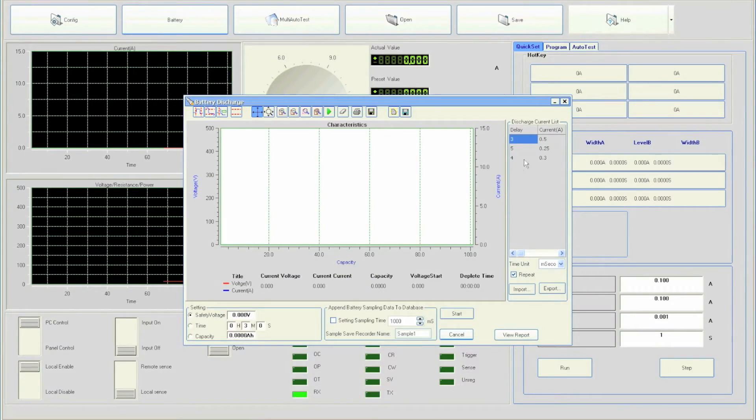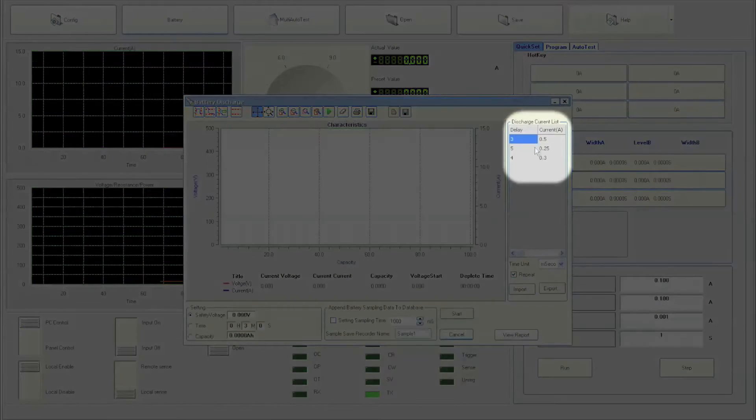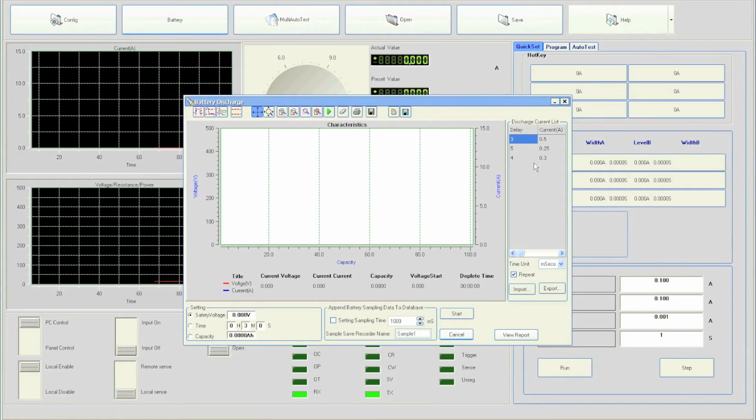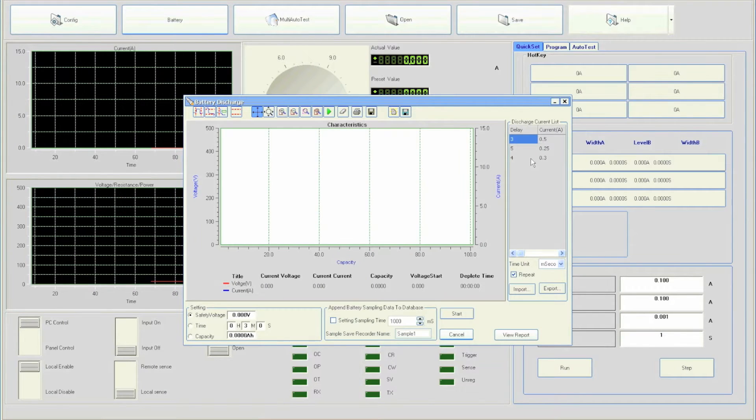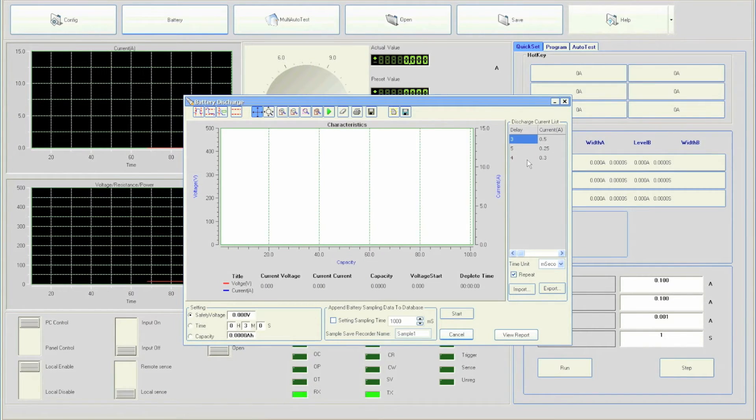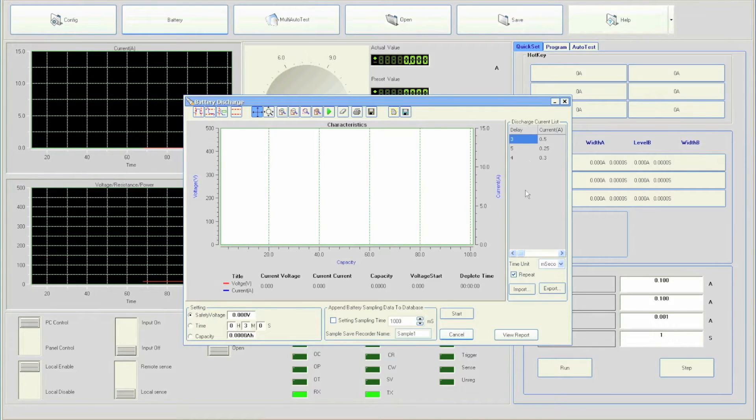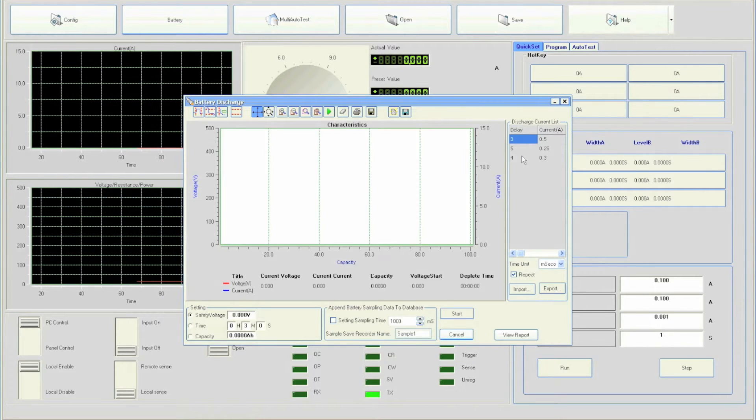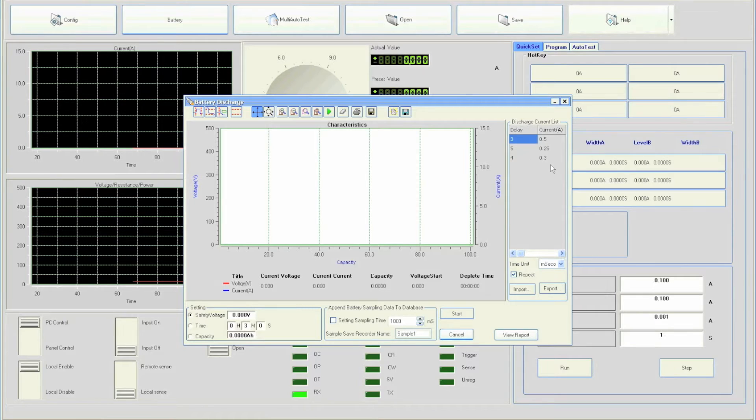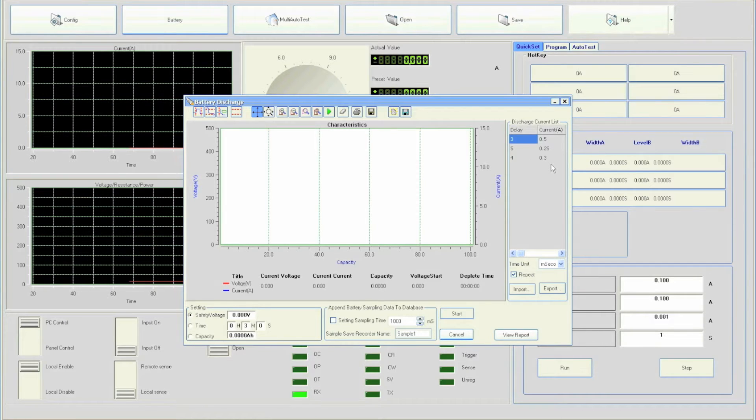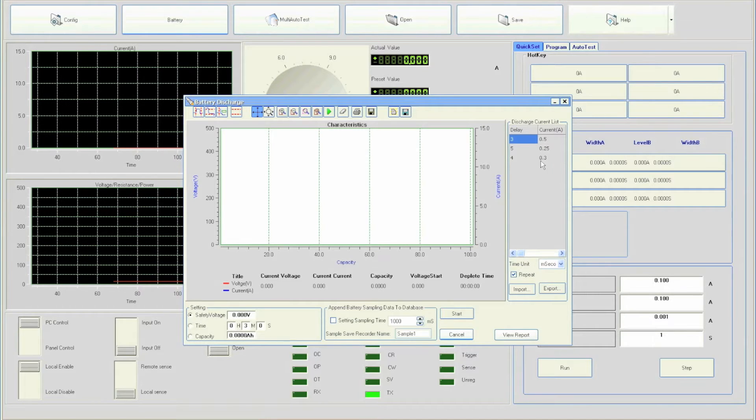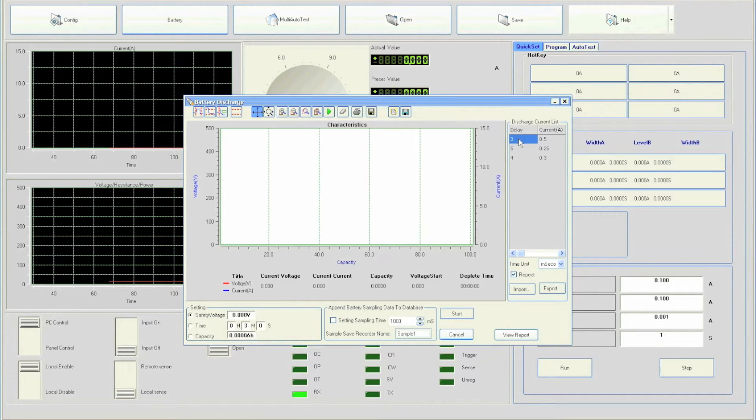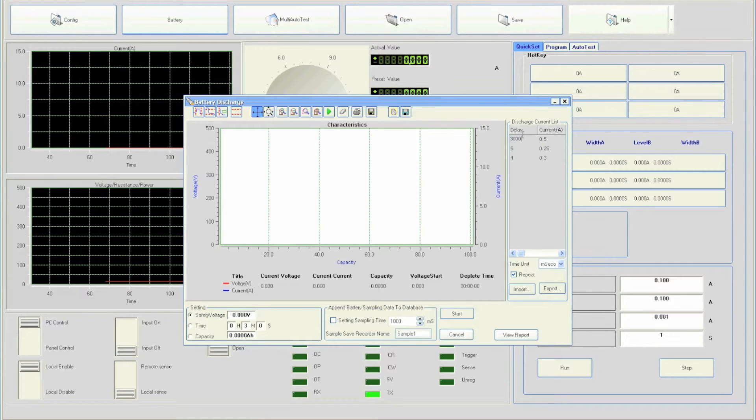On the right column, a discharge current list is available for users to create custom discharge profiles for dynamic testing. Let's enter a few steps in the list for testing. Keep in mind the left column specifies delay and right column specifies current. Users can enter the amount of time they want to hold a particular current value. We will first double-click the first row under delay and enter 3000.